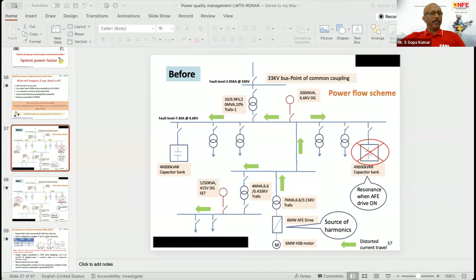Management asked to prepare various options, and finally the solution brought out was to remove one existing capacitor bank and put in a passive harmonic filter. During the measurement, the 7th and 11th components were found high among the higher harmonics. So for the 7th and 11th frequency components, a passive harmonic filter was installed in place of the capacitor bank, and the solution came to around 65 lakhs. My point is that such issues, even with this AFE drive, are a classic issue caused only by resonance. Mr. Ravi sir can put more emphasis on this. This was a very classic study which was performed.